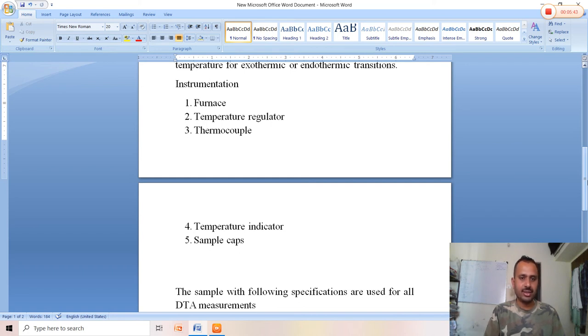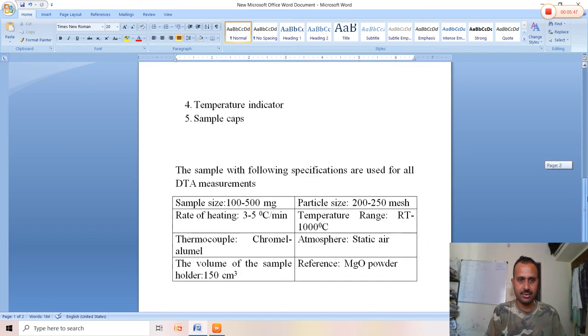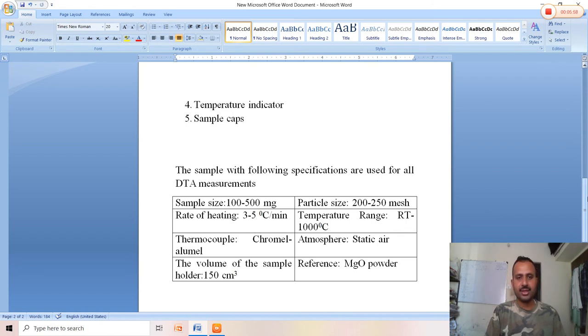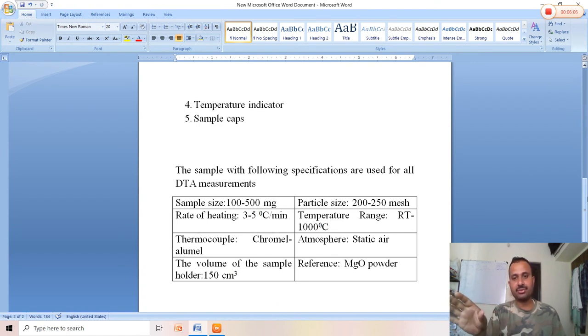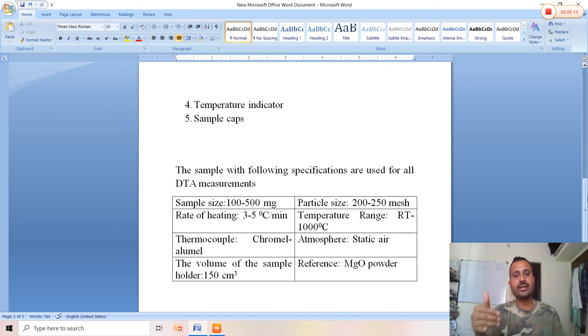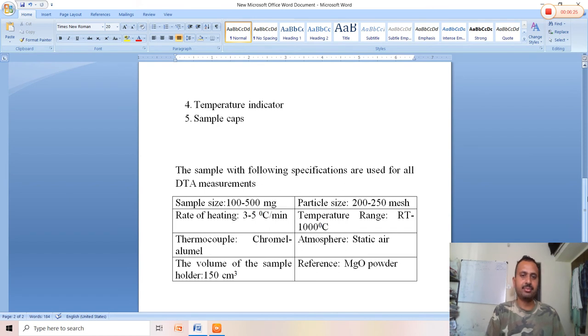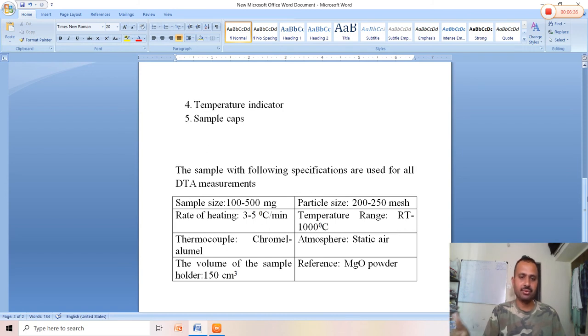The temperature indicator provides readings, and sample caps hold the sample. Samples with the following specifications are used for DTA measurements. Sample size: 100 to 500 milligrams. Particle size: 200 to 250 mesh. Rate of heating: a linear heating rate of 3 to 5 degrees per minute is provided, meaning for every minute the temperature rises 3 to 5 degrees uniformly.